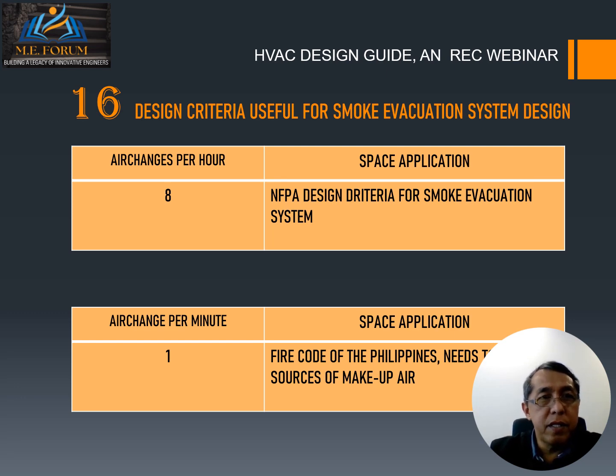Some bonus points. Number 16, design criteria useful for smoke evacuation system design. The NFPA design criteria for smoke evacuation is 8 air changes per hour. For our local fire code of the Philippines, you need to identify sources of makeup air, but the criteria presented there is 1 air change per minute.